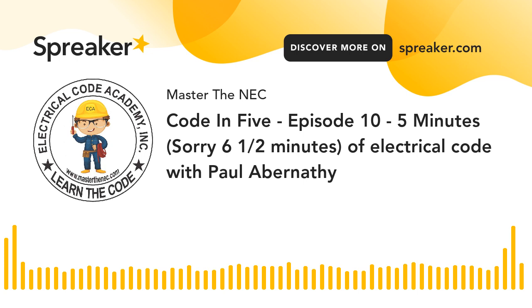Now, don't confuse that with the requirements for things like non-metallic sheath cable, which has its own limitations in 334.80, which is going to limit you to the 60-degree column, even though you can use 90 for adjustment and correction purposes. Don't get confused. We're talking individual conductors here, normal applications. The cable requirements under those specific articles are going to give you your own requirements.